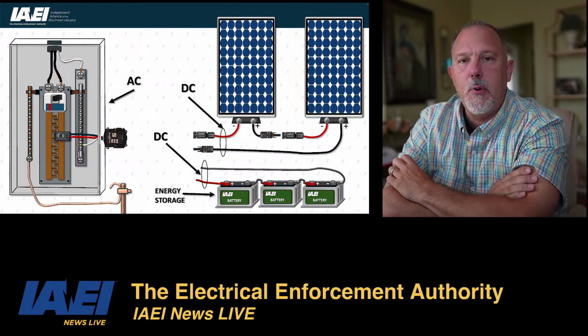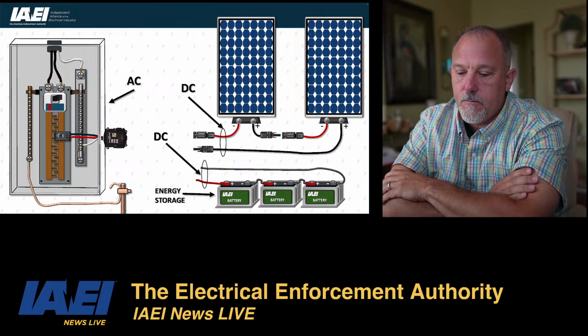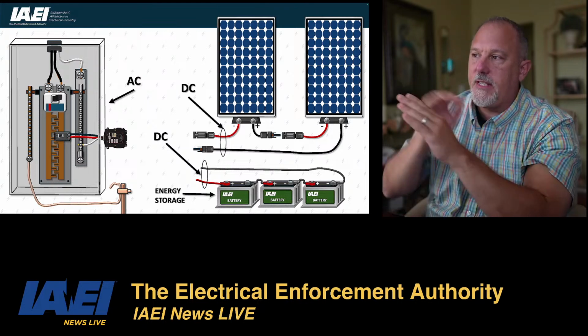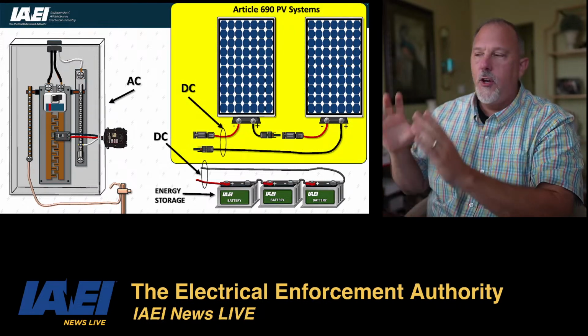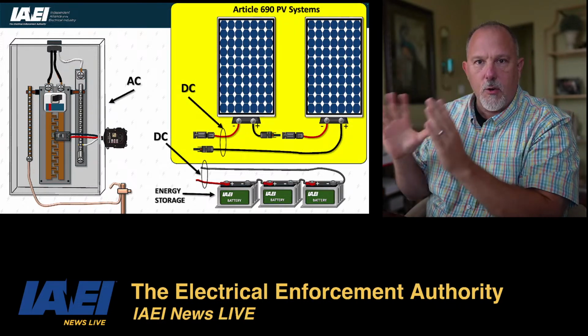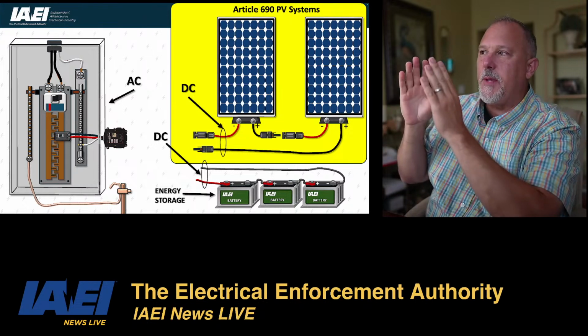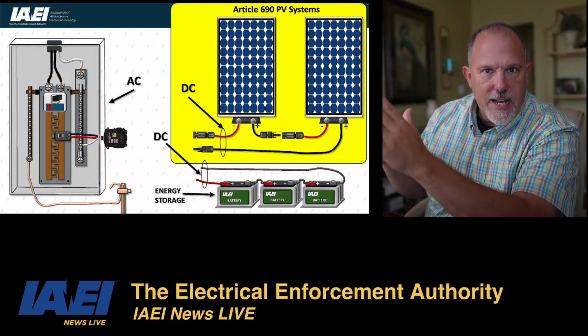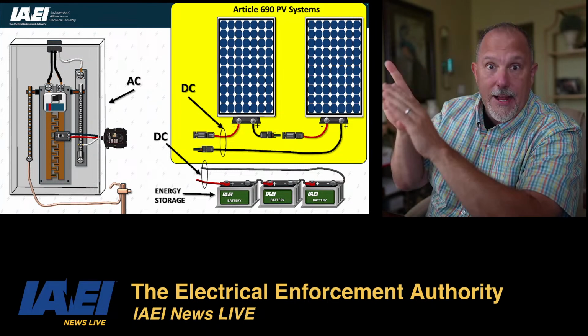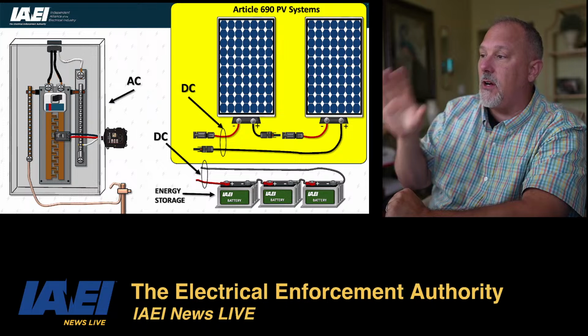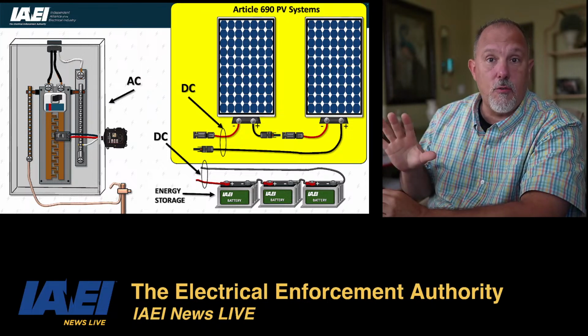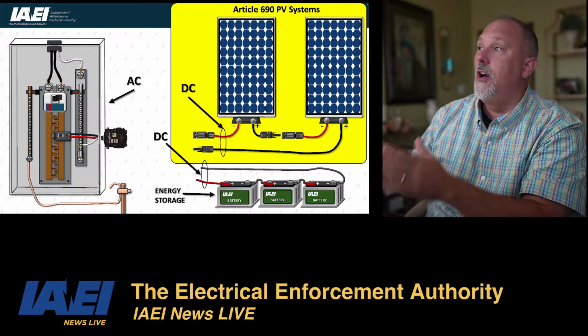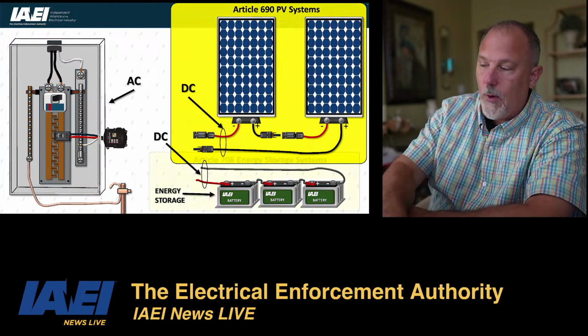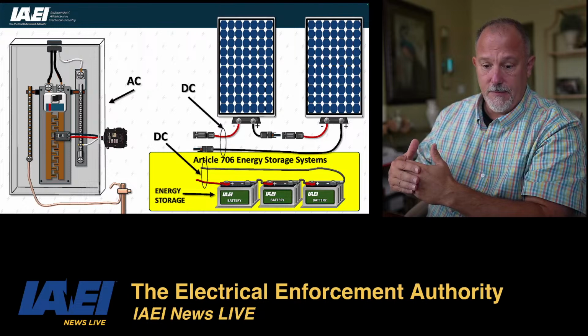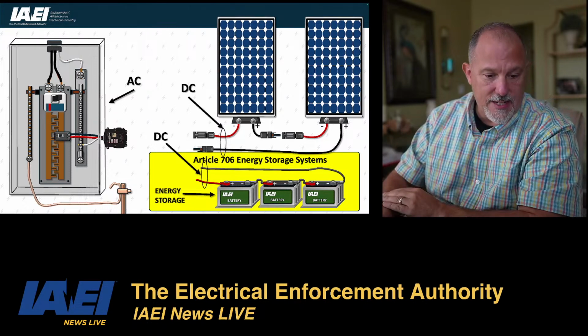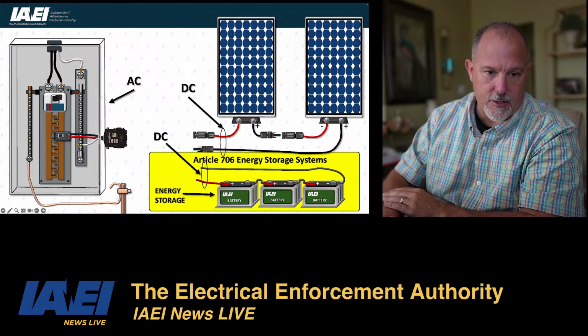You made a very good point this morning. When I think about these systems, that is an Article 690 system. I should be reviewing the photovoltaic installation with an eye on 690 to make sure that I am installing that system correctly. And Article 690 governs photovoltaic systems. When I think about an energy storage system, it's Article 706 that is my driving factor.